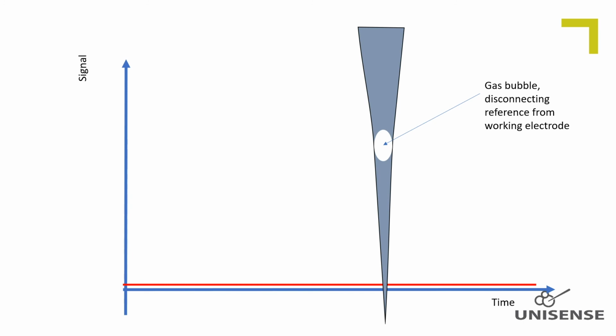There must be an air/gas phase in the electrolyte cavity in order to make room for temperature-induced expansion of the electrolyte. And if the sensor package was turned upside down during shipment, a gas bubble can be trapped in the tip. Such an air bubble can be removed by shaking the sensor like demonstrated here. The bubble will become loose and rise to the top of the electrolyte, and connections will be restored. In rare cases, a gas phase can evolve in the tip at the position of the working electrode, and such gas cannot be removed by shaking. So if there is no signal from the sensor, this could potentially be an explanation.